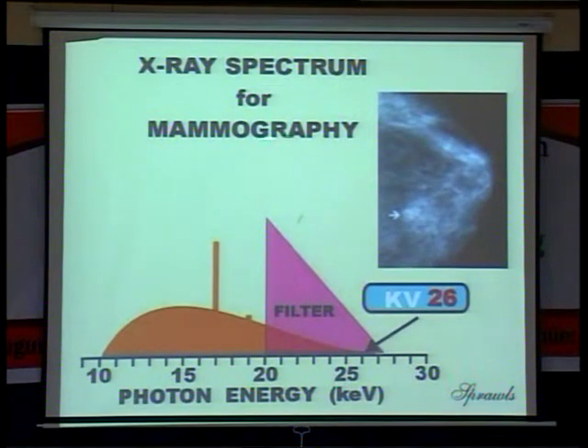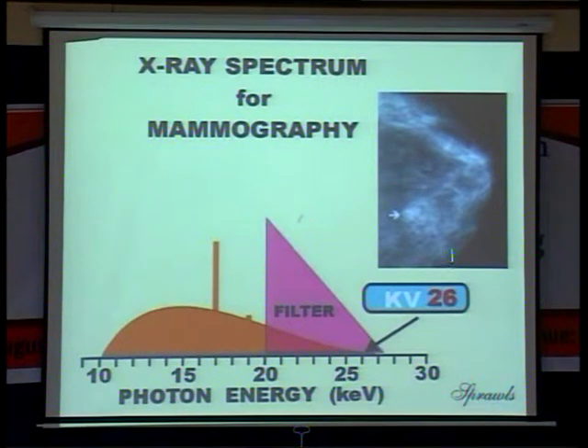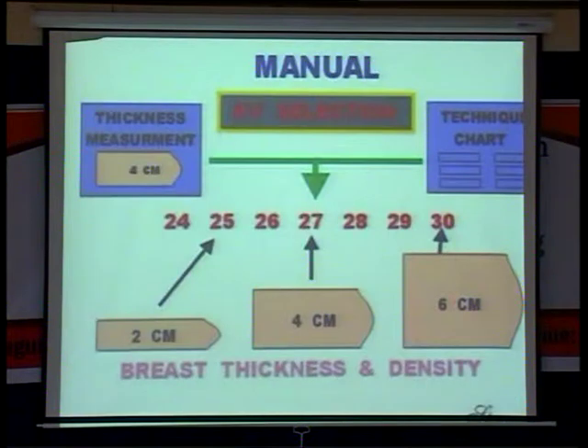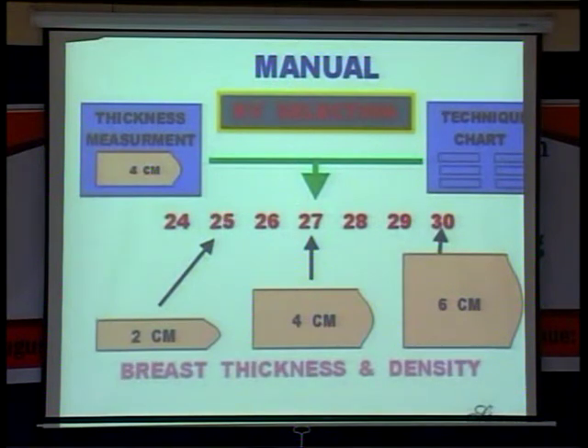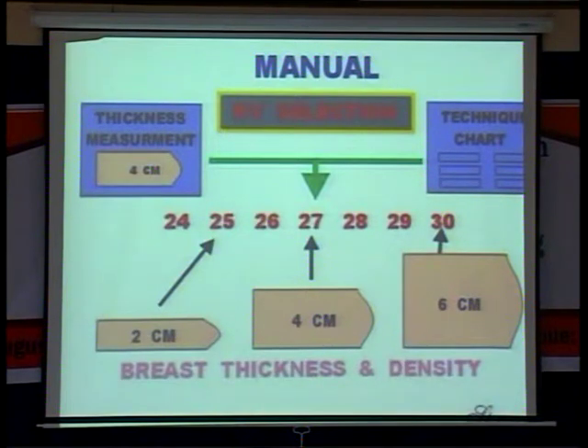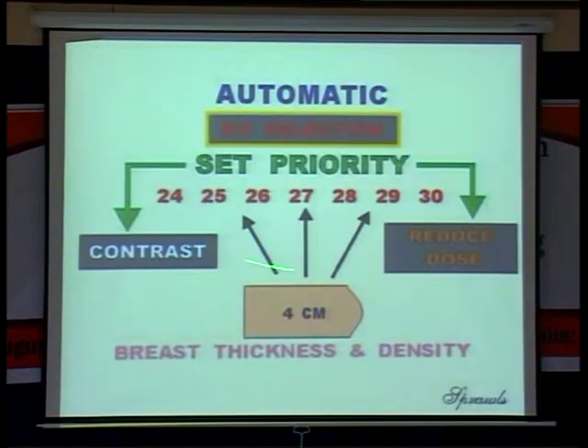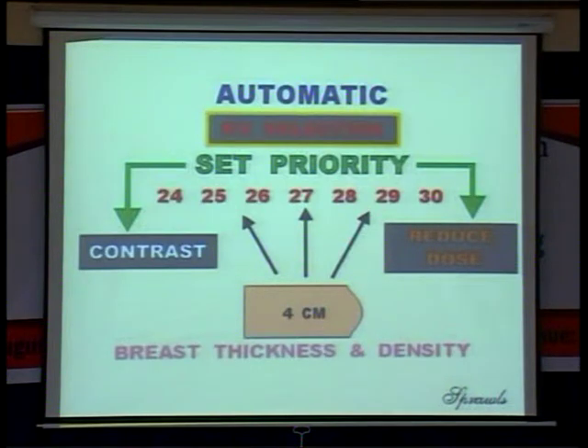Looking at the X-ray spectrum, you can see the photon energy for molybdenum and rhodium with the filter overlap. The ideal KV is around 26 KV — that is what the radiographer will use. Depending upon the breast thickness: for 2 cm breast you give 25 KV, for 4 cm breast 27 KV, and for 6 cm breast thickness the kV varies accordingly. Overall, breast thickness and density determine the kV, which varies from 25 to 30 KV. Automatically, it will set the priority for contrast and dose reduction in the automatic exposure control.